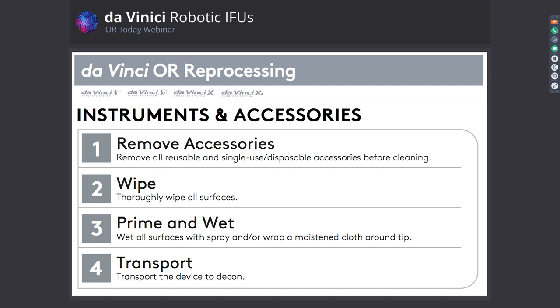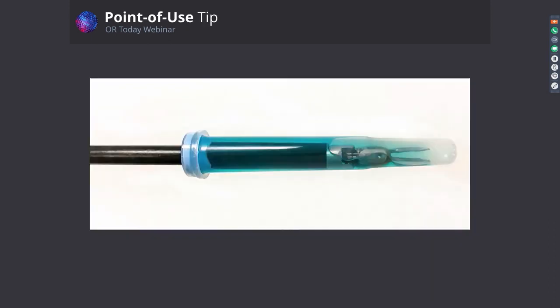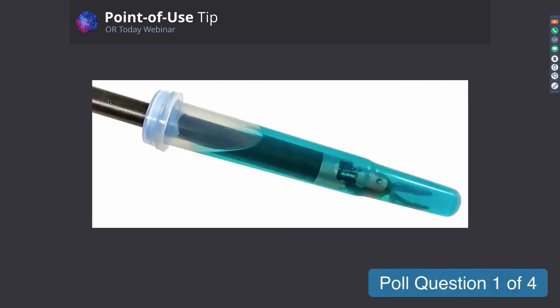One of the things that we see that I'd like to point out to you here is that if you're being vigilant in the OR and you're starting the cleaning process there, you have these vials that you insert the distal tip of the robotic device in. If you note in this particular case, this bubble has formed here and it's not quite cleaning the instrument, it's not touching there, it's not really allowing it to do its full job. Whereas if you tilt this instrument down, the distal tip is completely immersed in the detergent and it's starting the cleaning process.